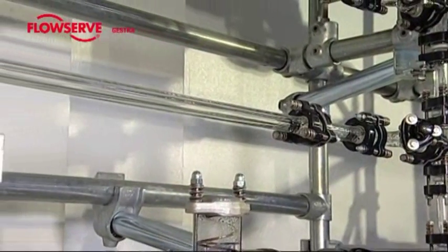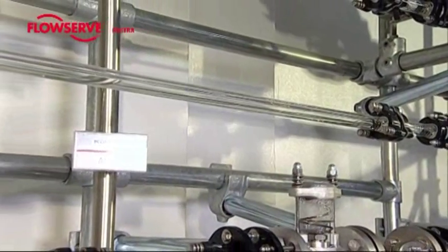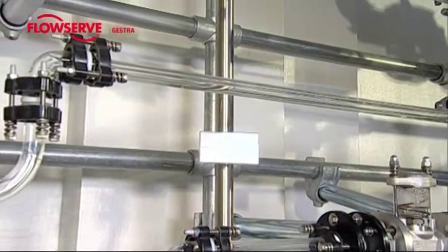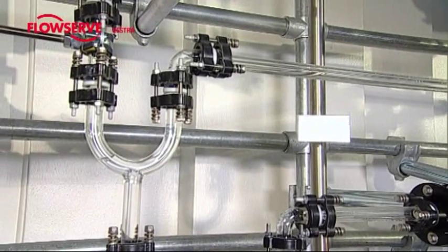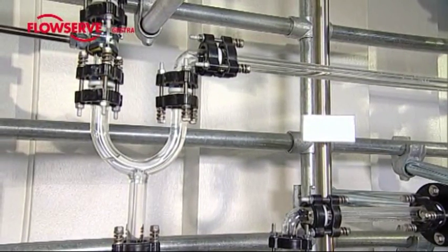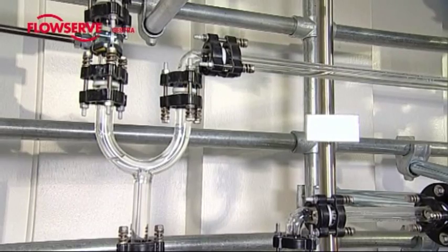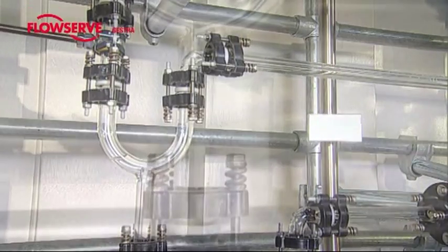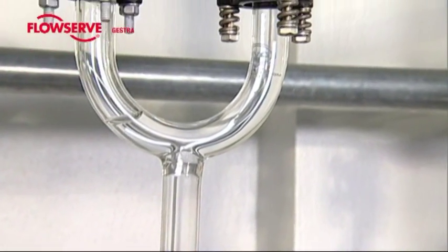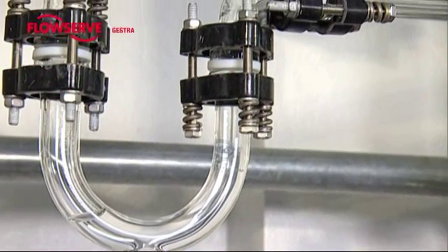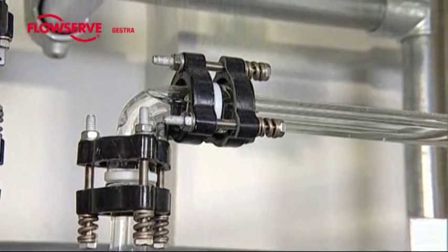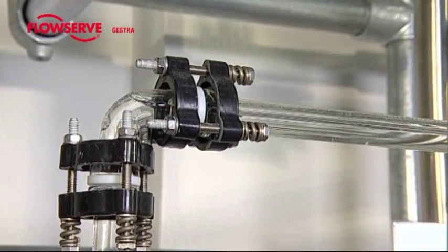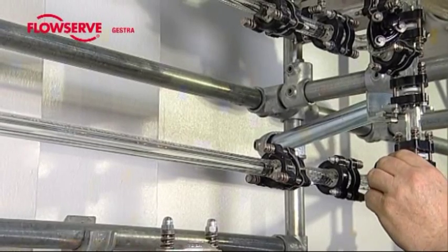The experiment is repeated a second time. This time, however, this part of the horizontal tube is arranged to have a slight drop towards a siphon. Having the siphon downstream ensures that there is always a steam bubble in the horizontal part and the water flows along the bottom. Through their volume, the steam bubbles at the top of the tube form a buffer space which minimizes the Waterhammer at startup and allows the startup process to be initiated faster and with less risk.